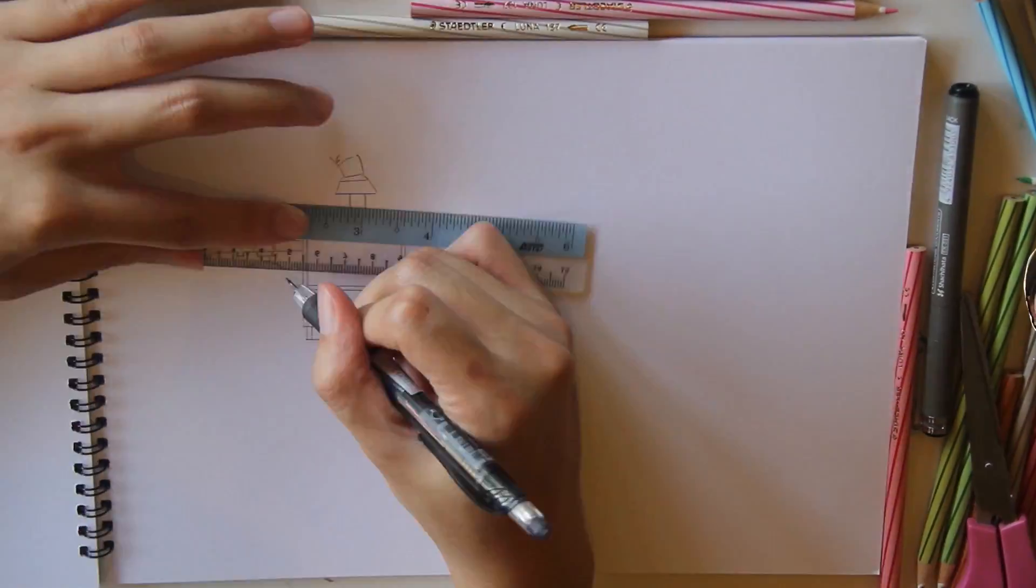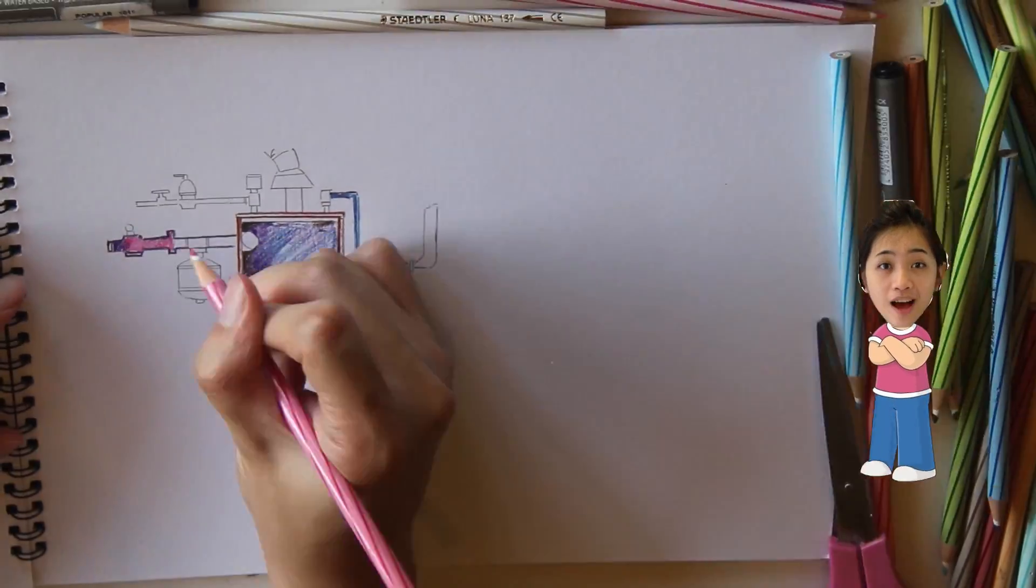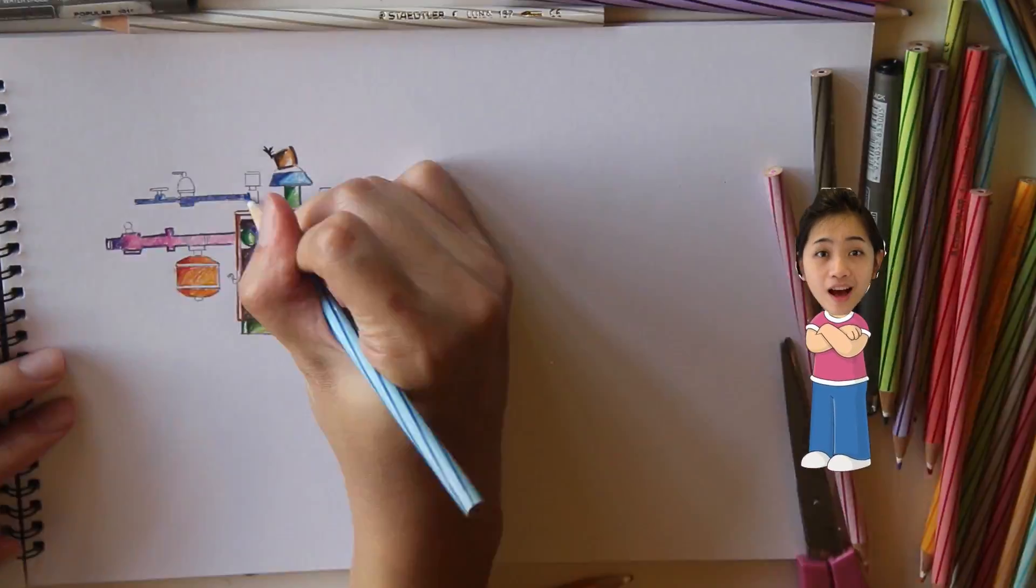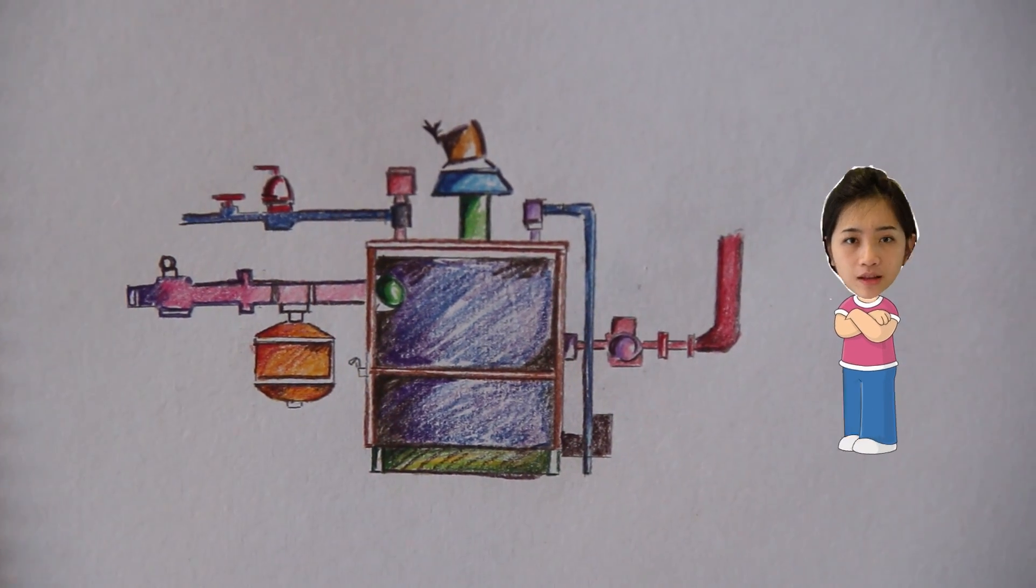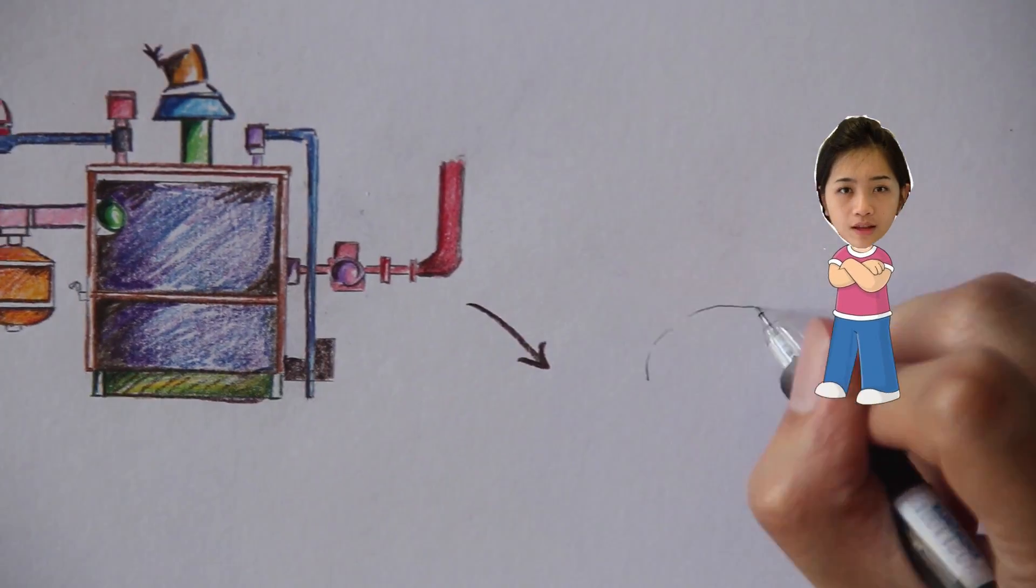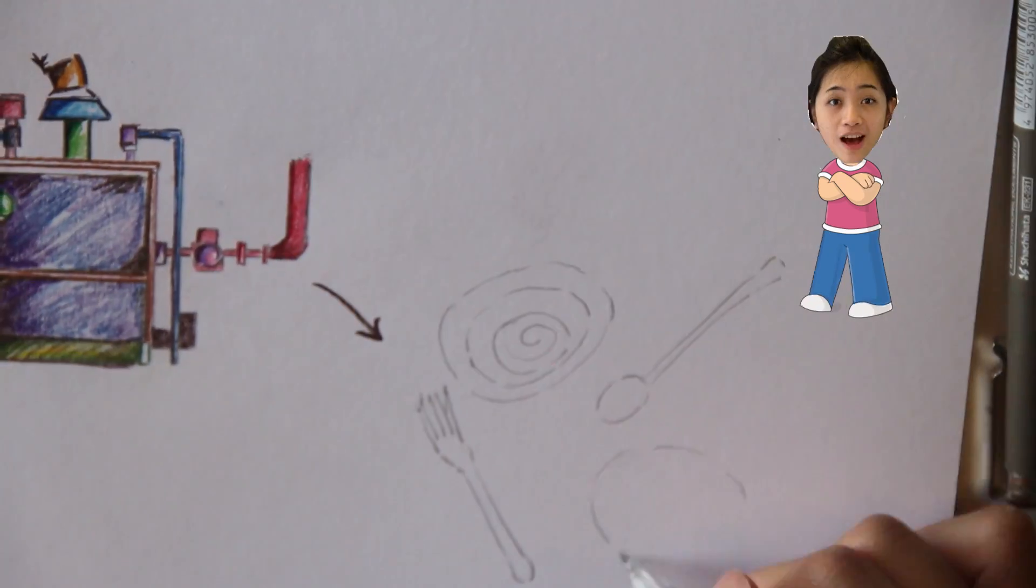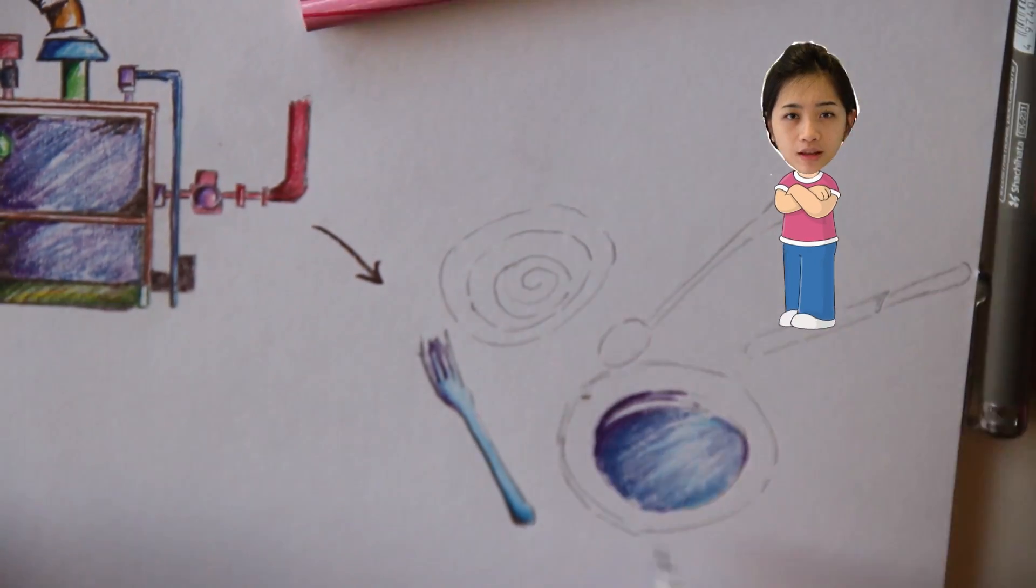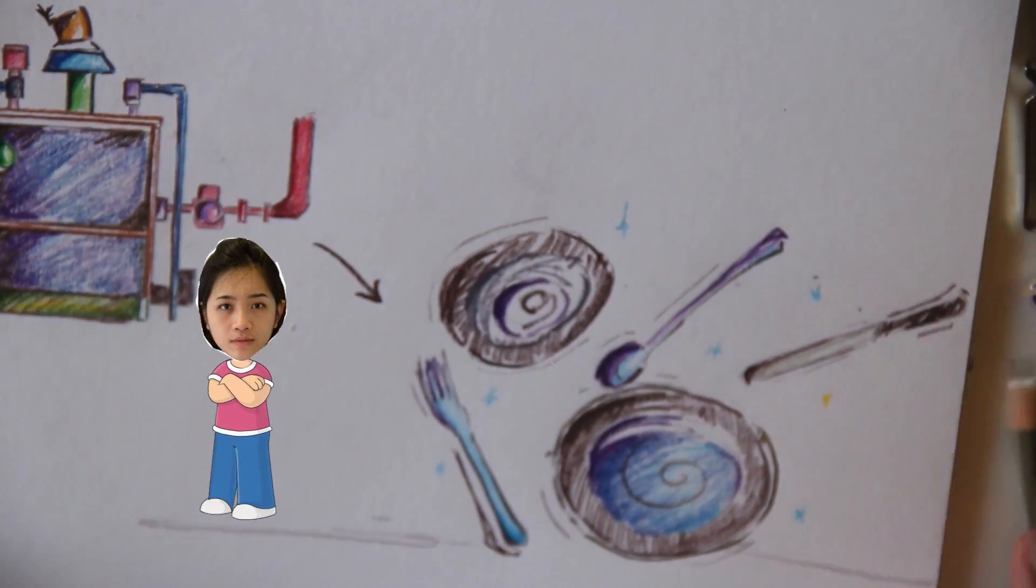The second one is hot water heating boilers. The process of hot water generation is quite similar to the steam generation process. The only difference is that the boiler generates hot water instead of steam. The input is fuel and feed water, where the outputs are the products of combustion and hot water. The pressure produced in the boiler forces the hot water to discharge through the main pipe. In hotel, this type of boiler is usually used as booster for the dishwasher in the kitchen. The booster is used to boost the temperature of regular water from 43 degrees Celsius to 82 degrees Celsius, because water at 82 degrees Celsius may be used as sanitizing rinse water to dishwasher.